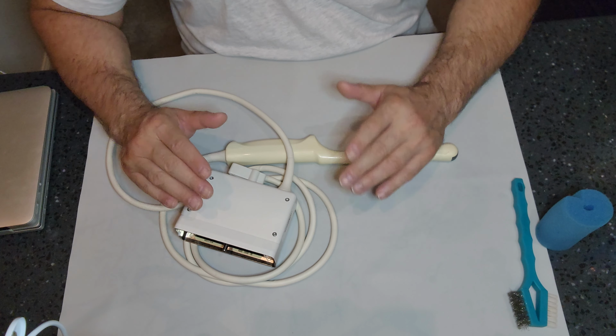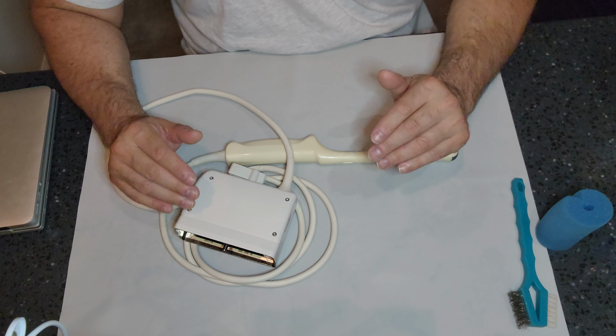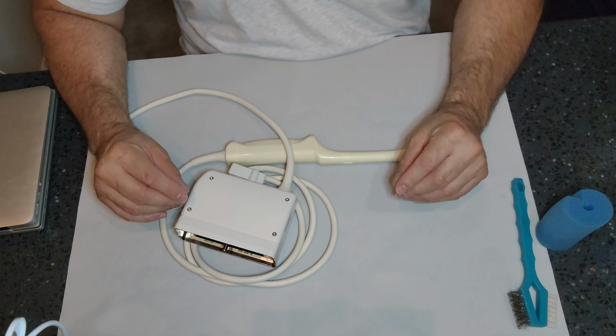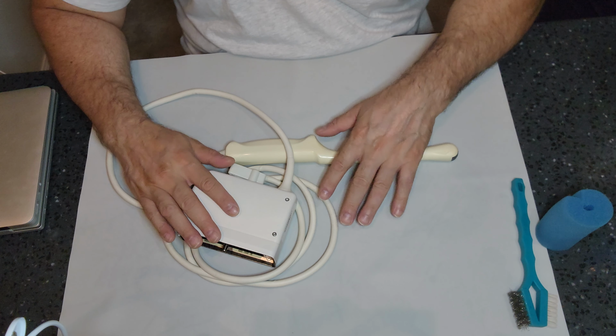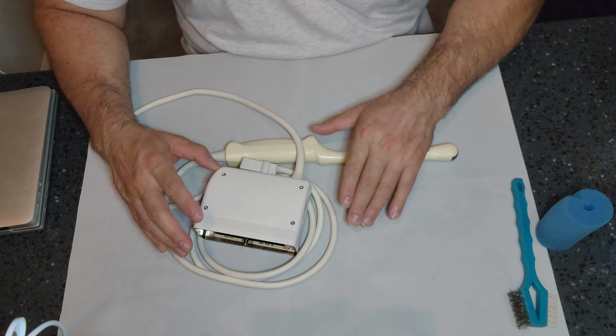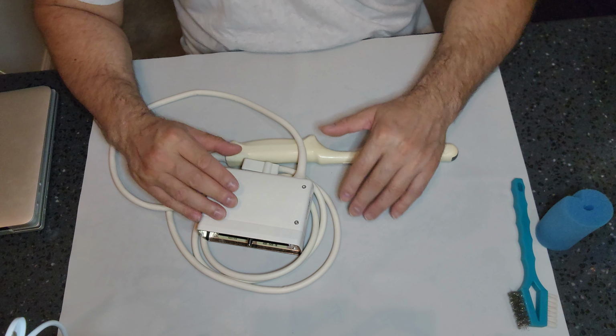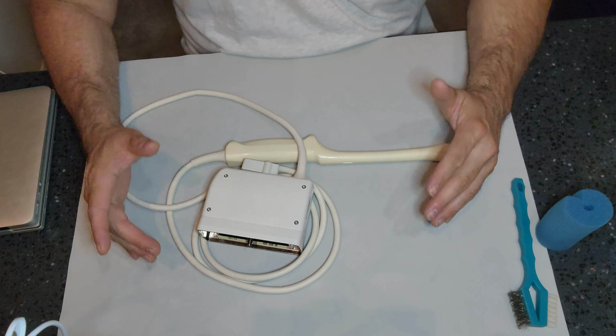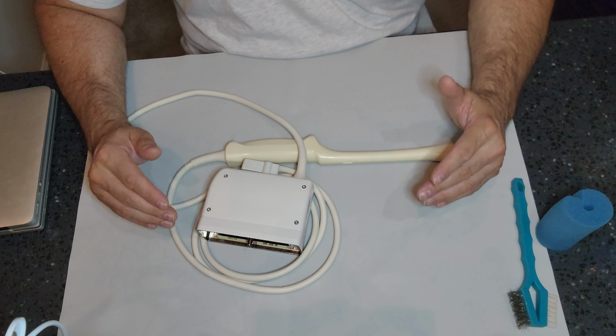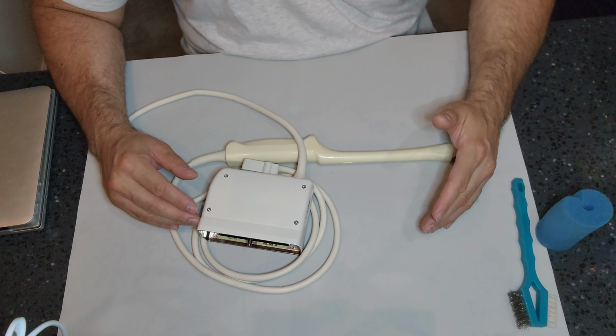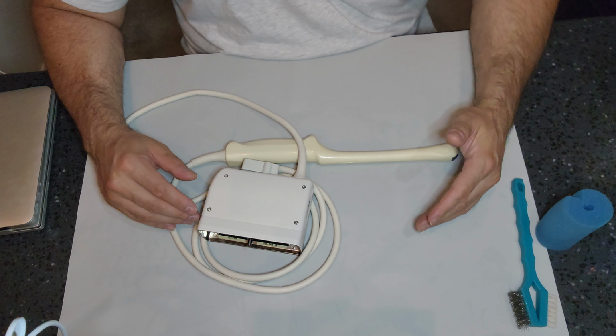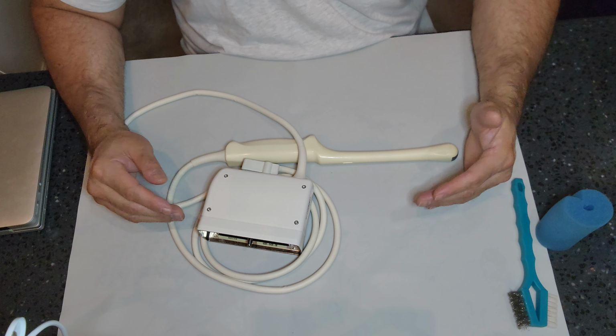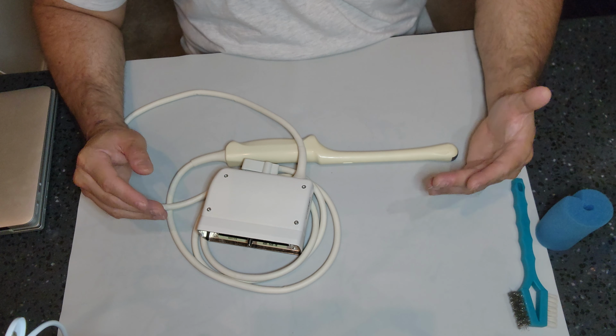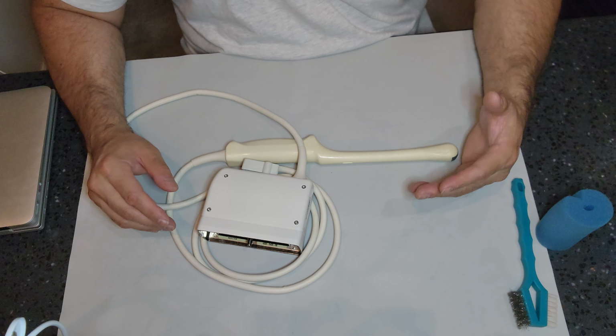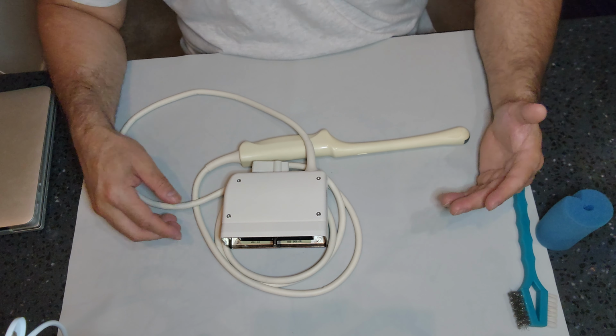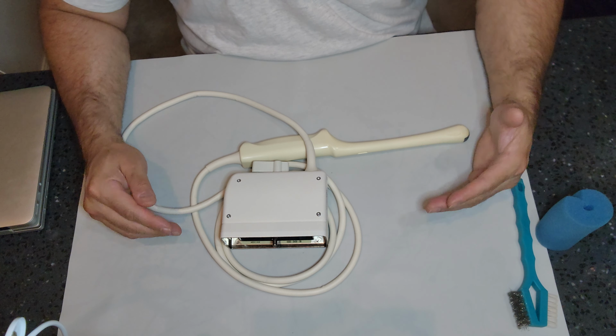Please, please, please refer to the IFUs. And why do I say so many pleases with the IFU? Probes are probably one of the few devices out there that the IFU is extremely broad. I think they almost validate every cleaner, disinfector, and sterilization process that is out there on the market. And the IFUs are very specific on probes, and I like that, and it gives you good choices.